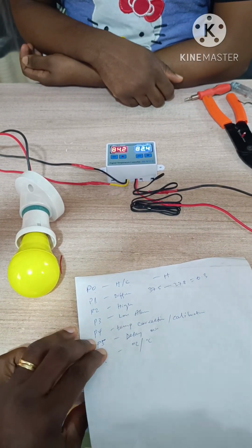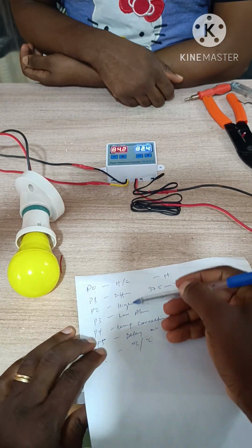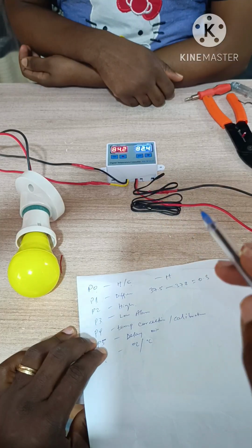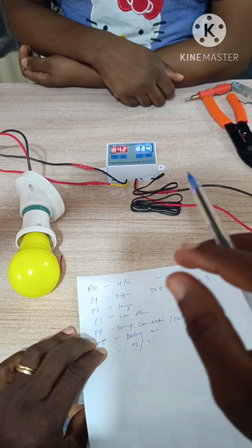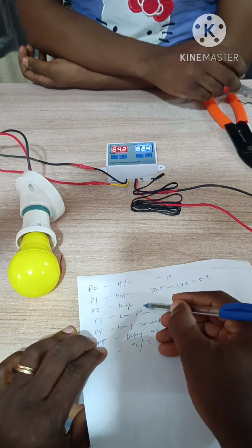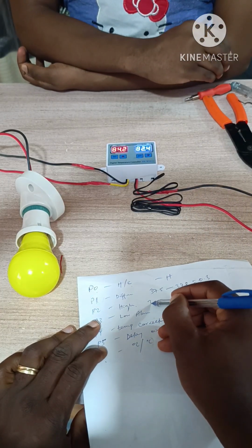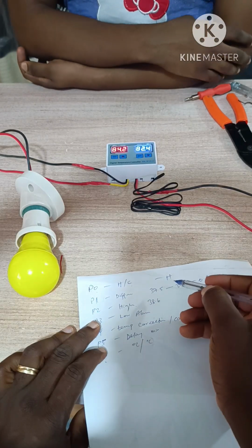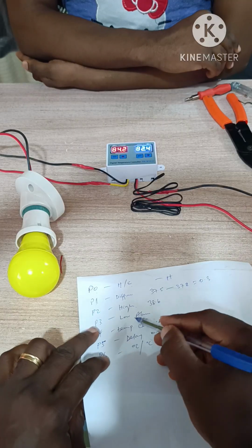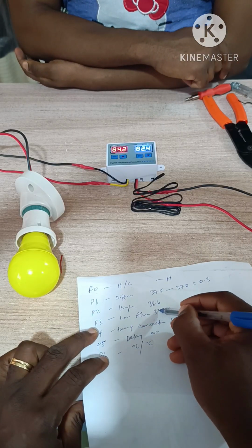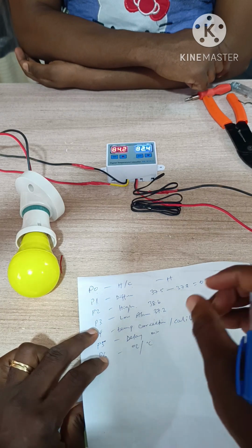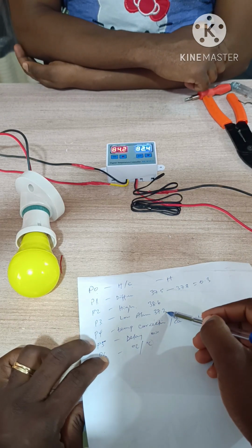P2 is the temperature high alarm. When you set the temperature, the number blinks, and it says the alarm is high. For the incubator, I call 38.6 and above my high alarm. Now the low alarm: I call below 37.2 a low alarm. When it reaches 37.2, it is in the low alarm.